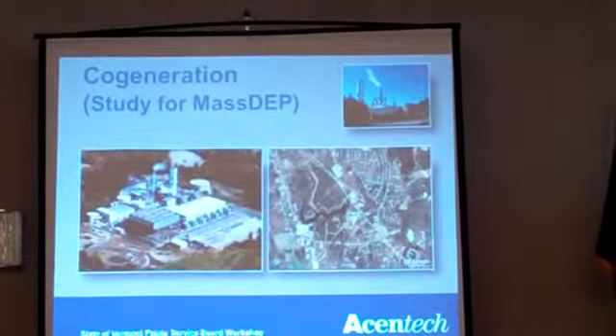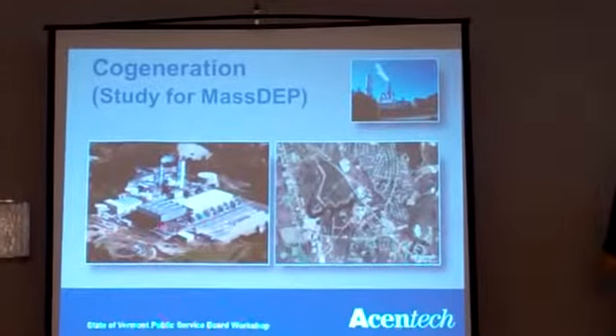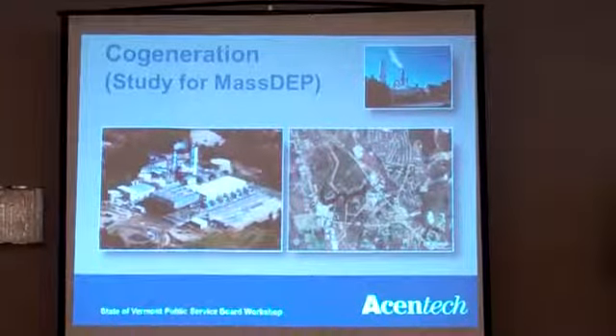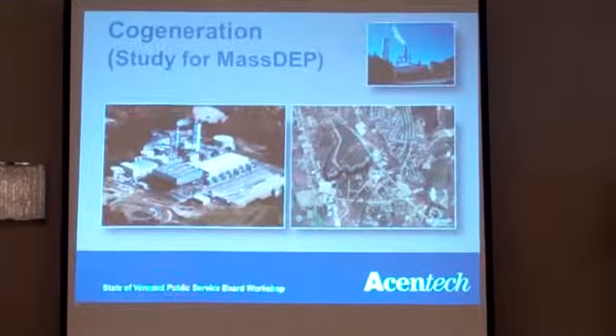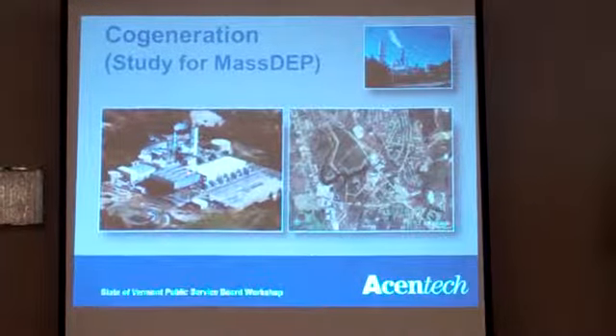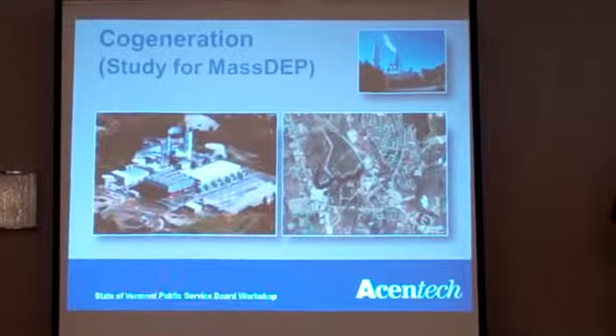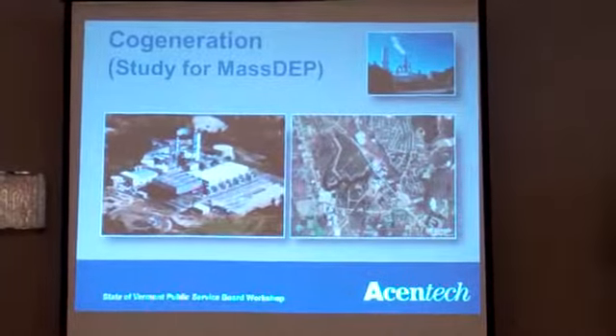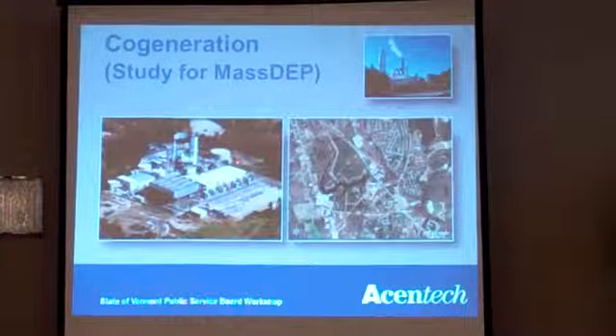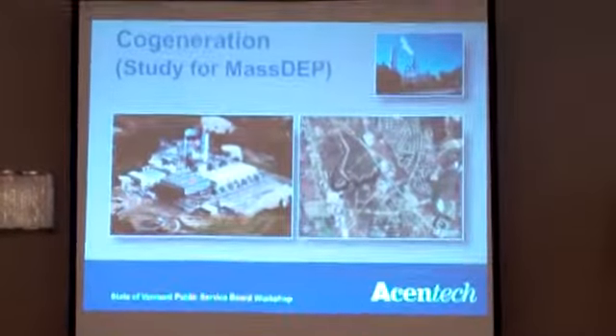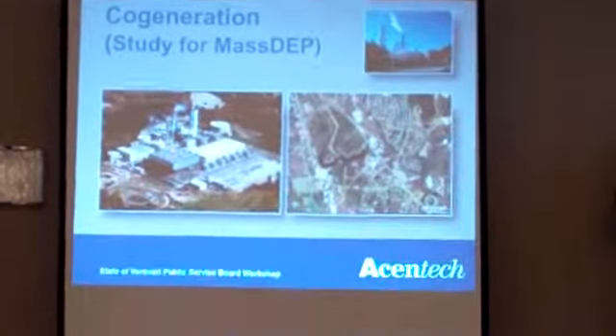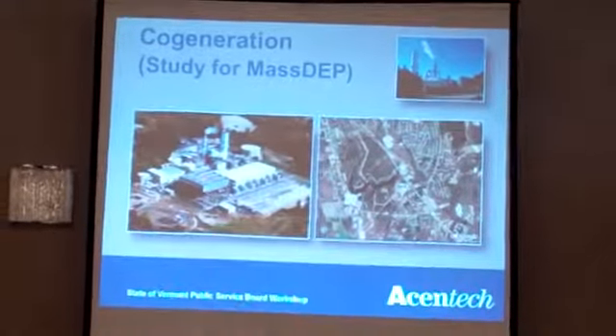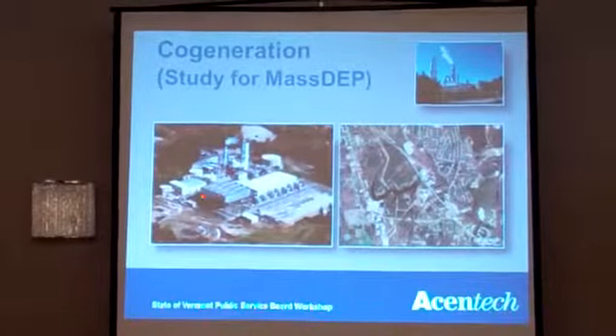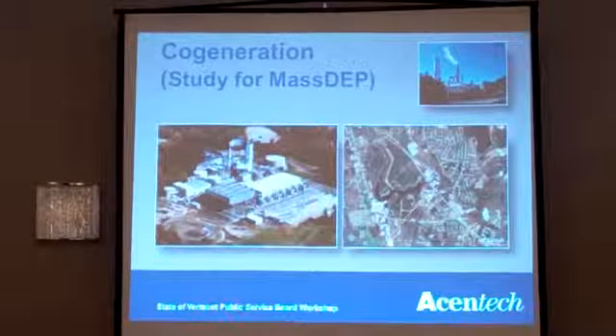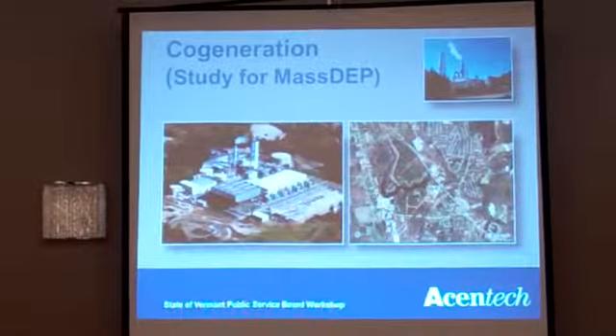One is an air-cooled condenser unit, basically a lot of fans with a radiator, again like your automobile radiator. At a plant of this size, that can account for half of the overall sound power level of the plant - as much as the balance of the entire plant. So it's worthwhile putting quite a bit of energy and money into quieter, larger, well-designed fans that operate at a lower tip speed.